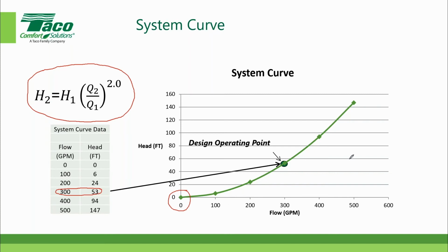If the pressure differential in the system is greater than what we had anticipated, the system curve bends upwards to the left. If the pressure differential in the system is less than we anticipated, it bends downwards to the right. And that pressure differential can fall along a vertical line, so I just throw in a vertical line here so you can see what that looks like. So if the pressure, instead of being 53 feet at 300 gallons per minute, is greater than that, perhaps it's over here somewhere. I'm just going to put a dot up here. Maybe that's like 90 feet.